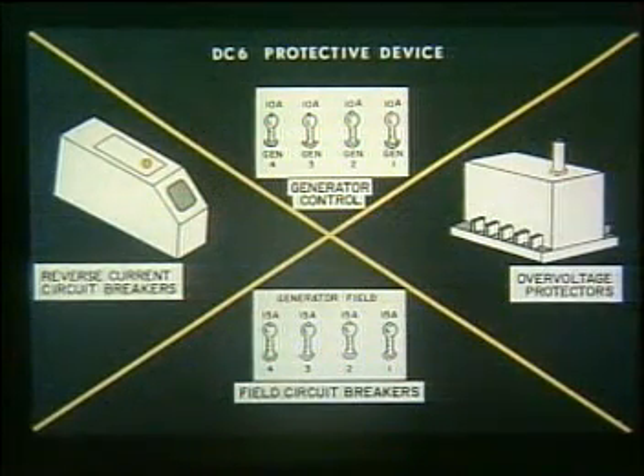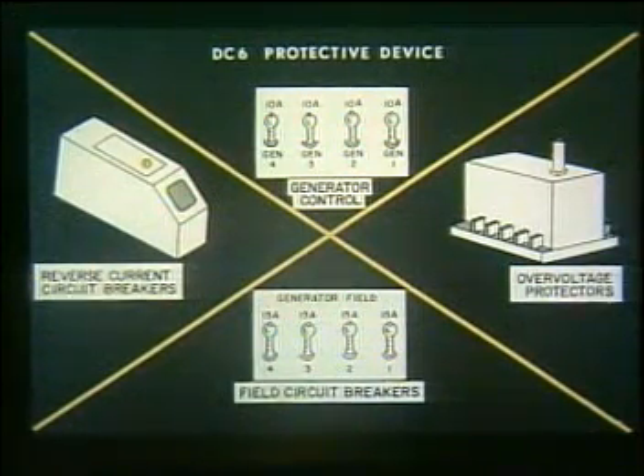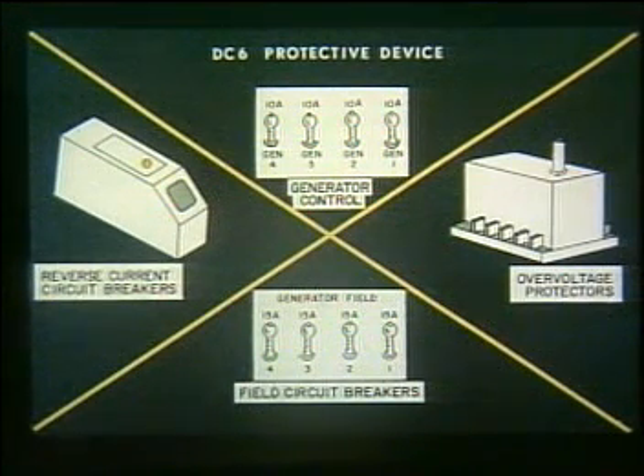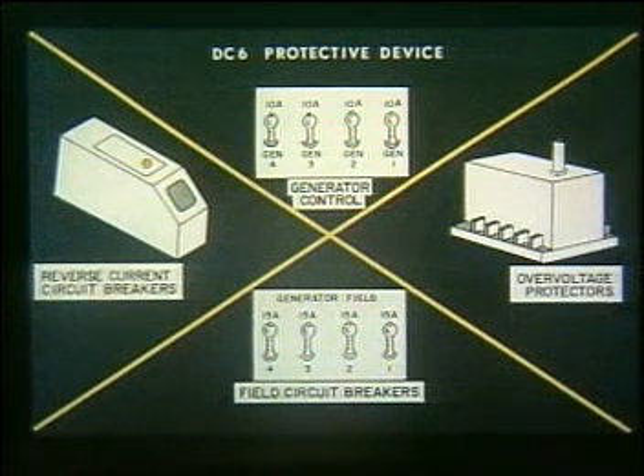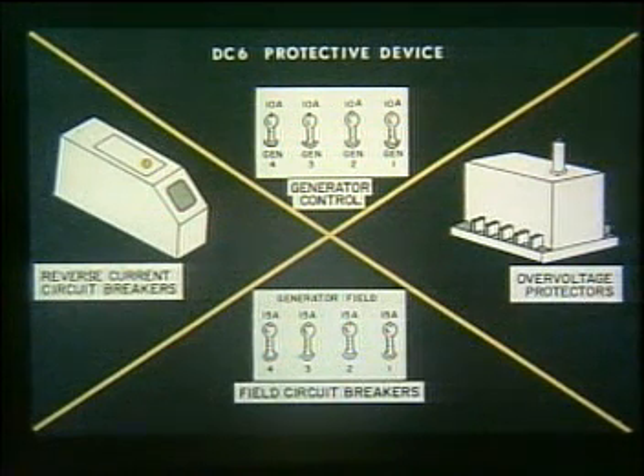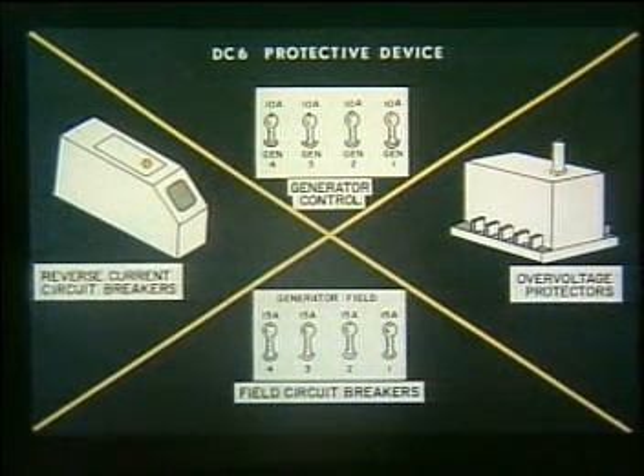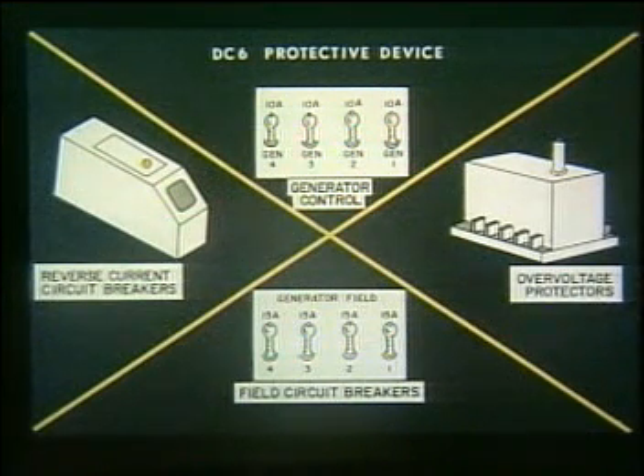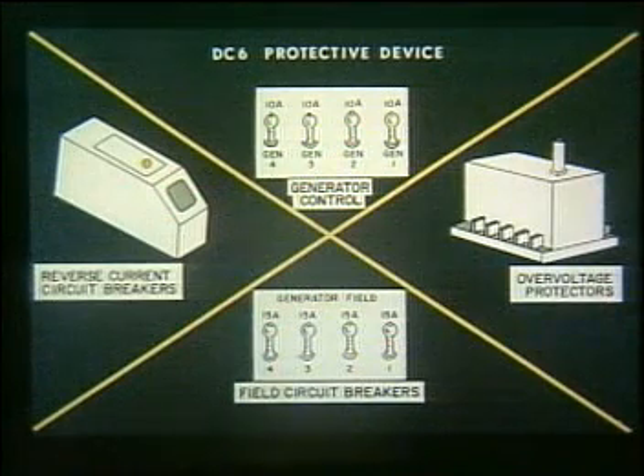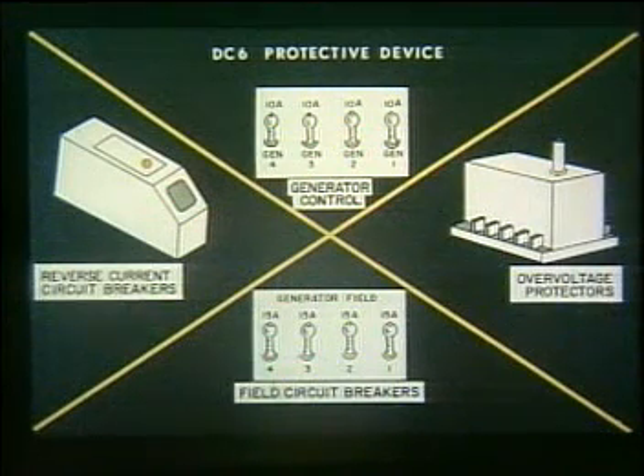The generator control circuit breaker protects the bus and generator from a malfunction in the generator control panel or the generator field. The overvoltage protector will trip on full field voltage application and removes the generator from the bus. The field circuit breaker will trip with a heavy current flow in the generator field. It is also the only manual method to open the generator field. When tripped, it will remove the generator from the bus. The reverse current circuit breaker trips at 300 amps reverse current and removes the generator from the bus.